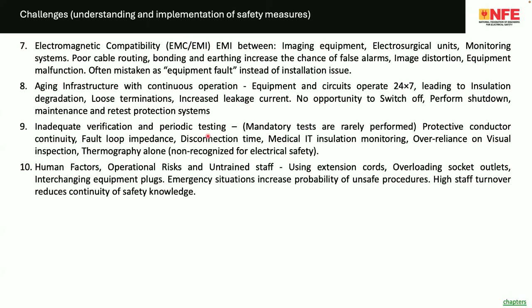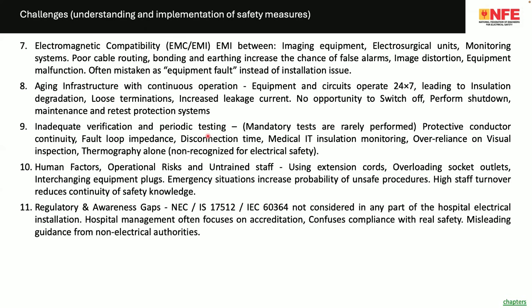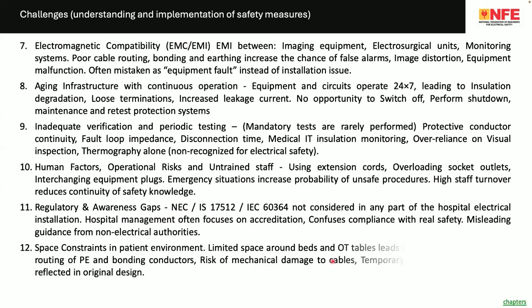Human factors, operational risk, and untrained staff is also example. In some hospitals, if we go and ask the maintenance staff, where is your electrical distribution? In most cases, the answer is not encouraging. Regulatory awareness and gaps. In fact, compliance to the standards and regulations are necessary, but in most of the cases, violations are happening. Space constrained in patient environment, because that means there is a limited space. As a result, the wires are hanging, the wires are on the floor, the plug points are not proper, multiple plug points in one socket.